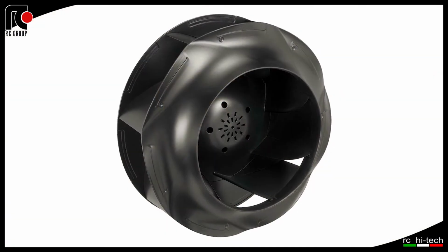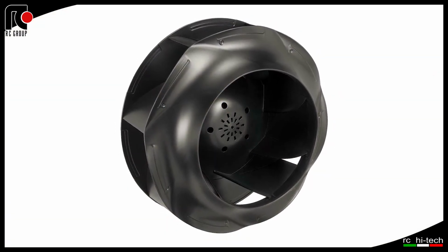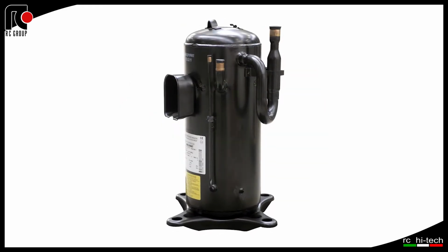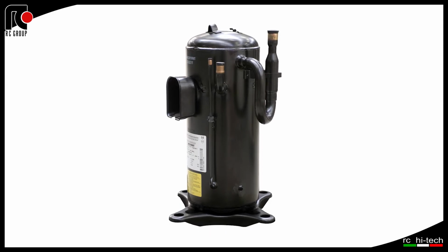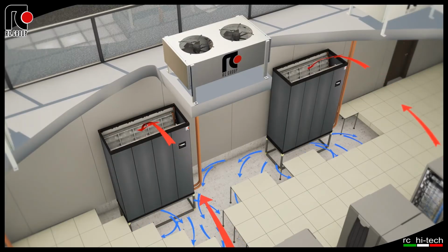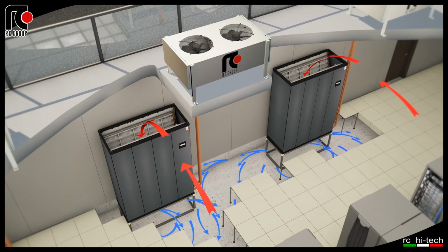Main components for each air conditioner are EC electronically commutated plug fans and inverter-driven scroll compressors with stepless capacity control. The combined operation of the inverter-driven compressor and EC fans respond in real time to thermal load changes within the data center and realize substantial energy savings.